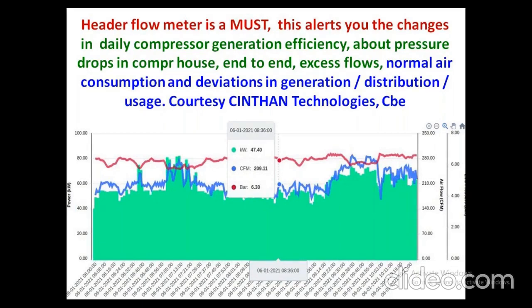So to maintain the pressure drop, this mill is always keeping 1 bar high on the header pressure. You are going to use the cleaning for a given mill daily, say 4 hours. And for 4 hours of cleaning, you are keeping the compressed air header at 1 bar more pressure for 24 hours. That is a loss to the mill. You have to educate the mill to keep a dedicated cleaning receiver, so the pressure does not drop when cleaning is happening. Schedule the cleaning. That is more important.